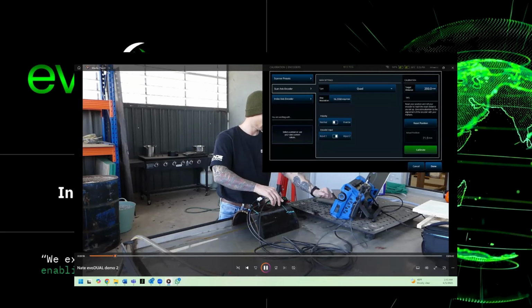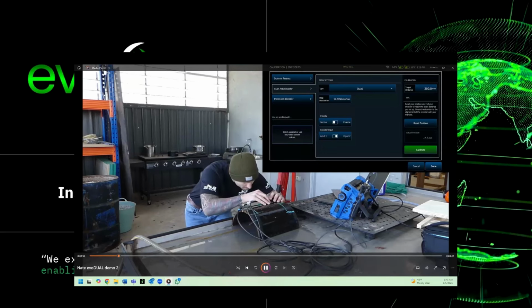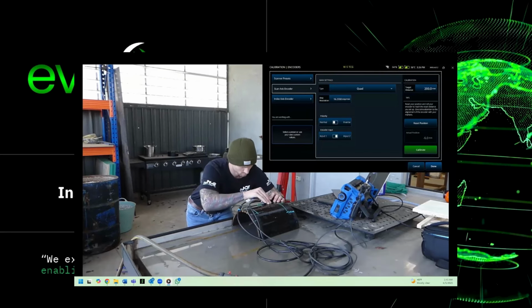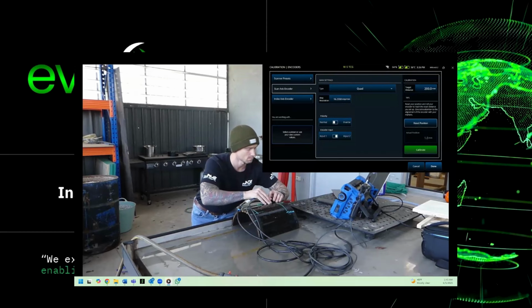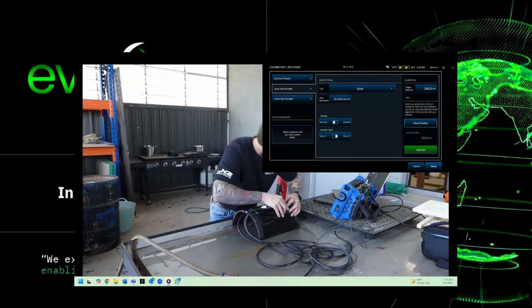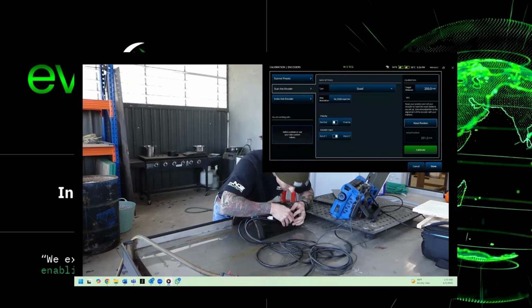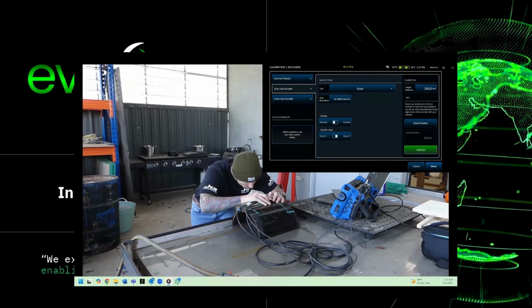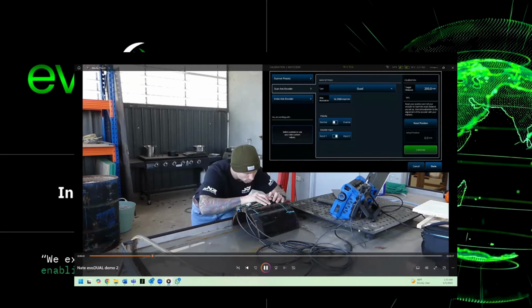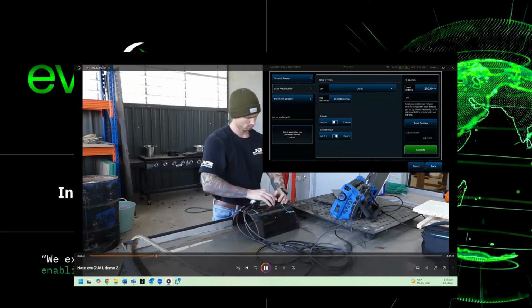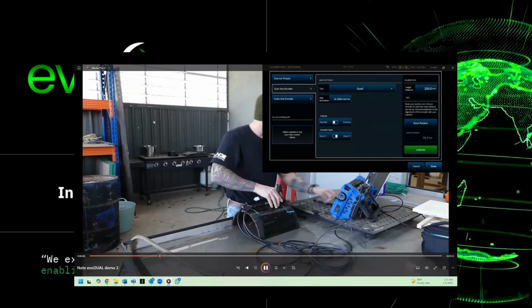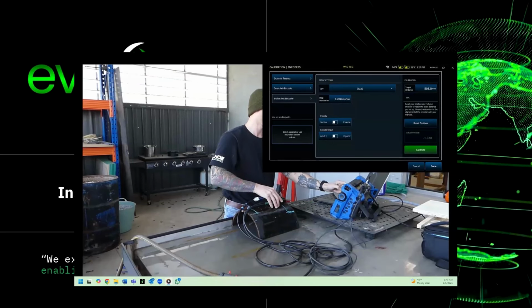So we're punching in the target distance. I'm going to set the dual or the arc dual to 0, clear the position out, and then push it down to the target distance that I'm aiming for, which is 200 mil here. I'm about 1.7 mil off, so I just calibrated that. Now I'm going to scan back to 0 and confirm that the resolution is correct here. I'm satisfied that was dead on 0, so we're going to move to the evoDUAL, which is my index axis encoder, excuse me. And that type is quad as well.